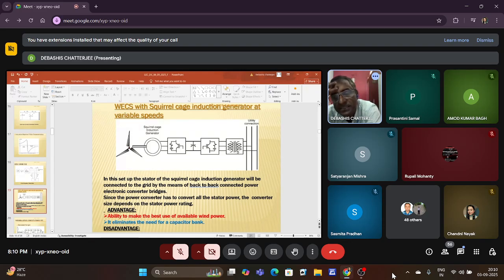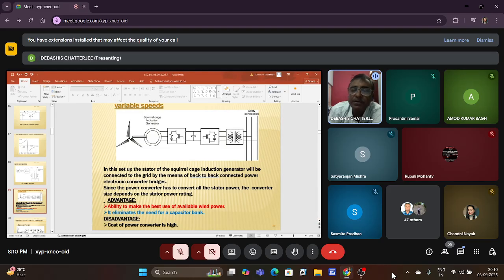Now again, you see, this system will have a similar drawback: it will require two large converters of equal rating to that of the induction generator, isn't it? Induction generator 1 megawatt, this active front end converter has to be 1 megawatt, and this grid side converter has to also be 1 megawatt. So again, high cost, high space requirement, and reduced reliability, everything is there. So the cost of converters is high. This is the major disadvantage.